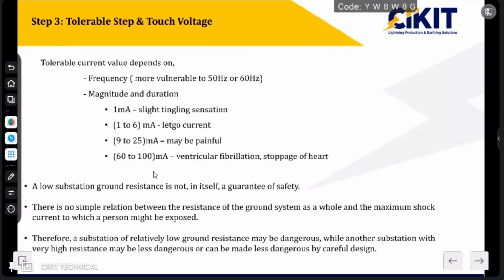Apart from that, the other parameters which influence the damage to the human body are the magnitude and the duration of the fault current. If a fault current of 1 milliamp flows through our body, we will have a slight tingling sensation. If the magnitude of current increases from 1 milliamp to 6 milliamps, that is called the let go current. Let go current means we will have the sensation that current is flowing through the body, but we will still have the consciousness to remove our hand. If our hand is on a live object, we can remove it from the engaged object. So that is called the let go current.